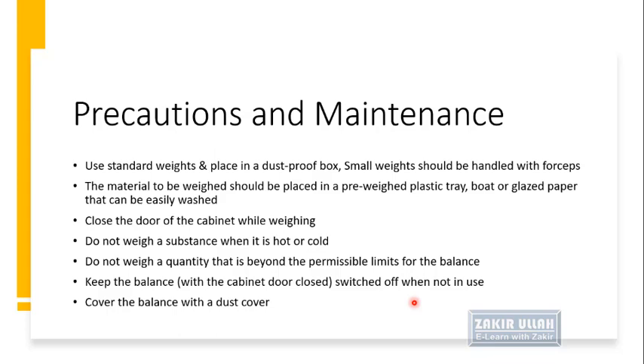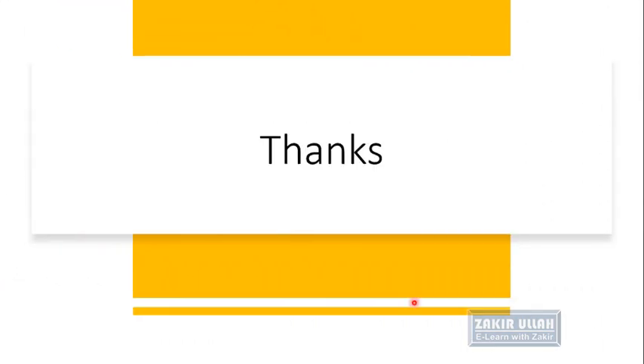Close the cabinet door while weighing any object. Do not weigh a substance when it is hot or cold, as the reading can vary when it returns to normal temperature. Do not weigh a quantity beyond the permissible limit of the balance — every balance has a minimum and maximum capacity. Keep the balance with the cabinet door closed and switch it off when not in use. After use, cover the balance with a dust cover.